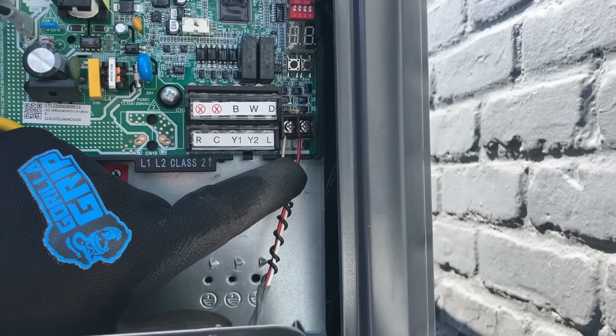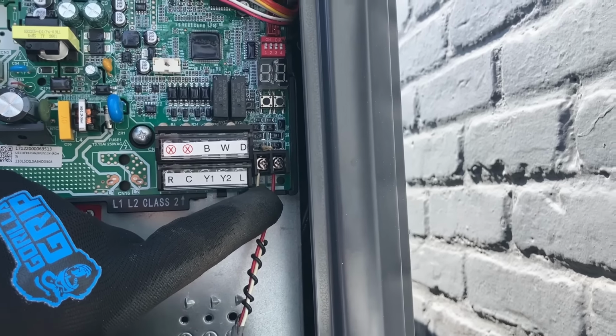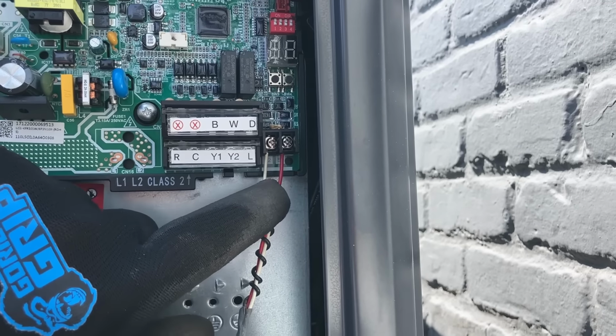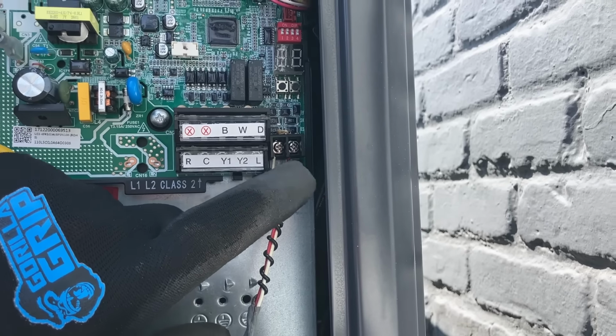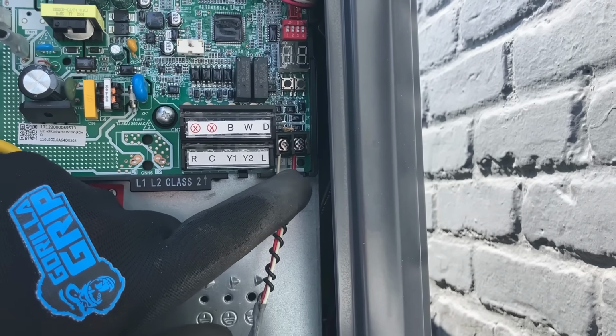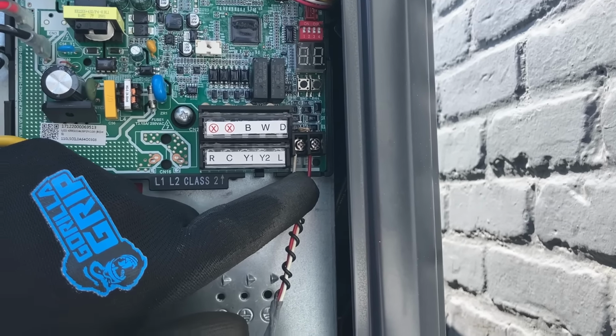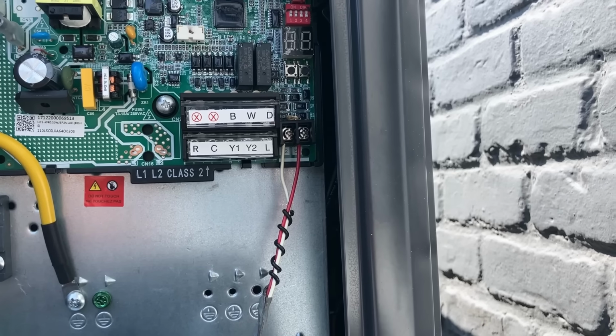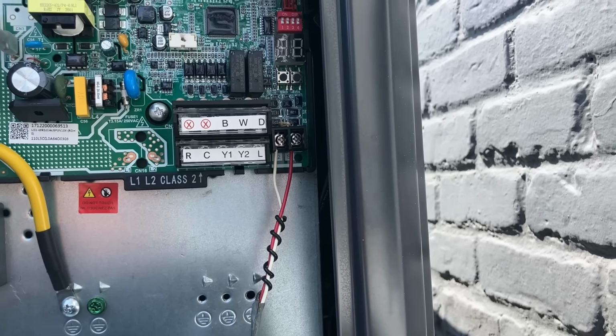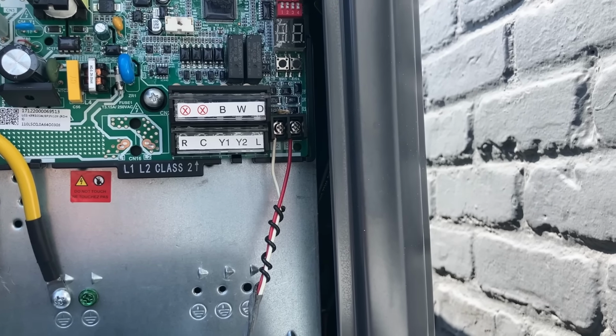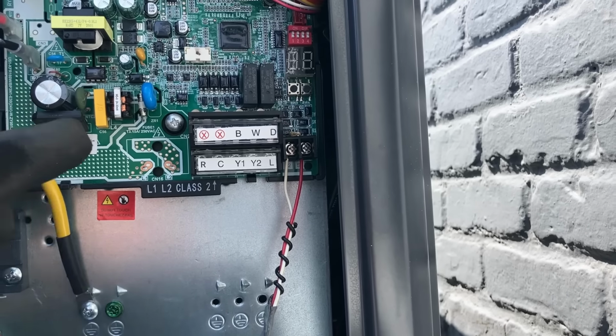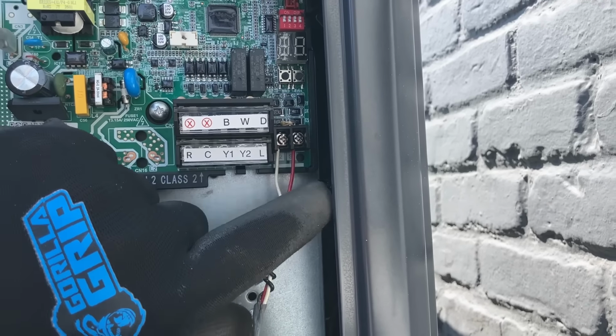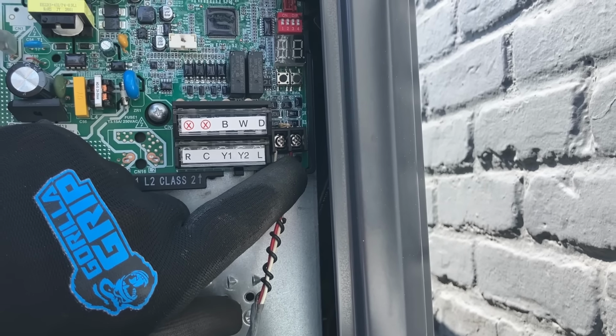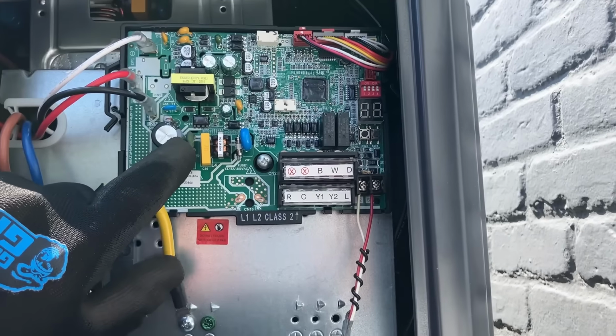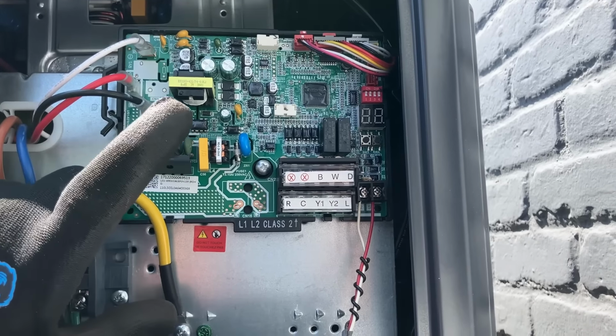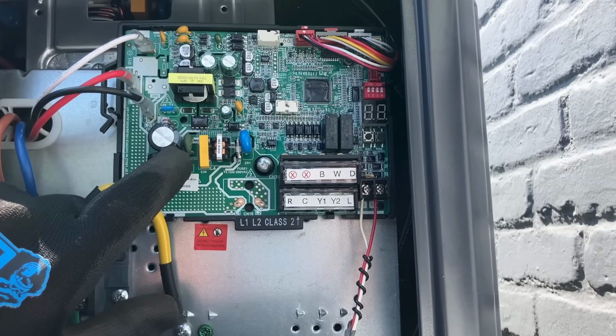These 2 wires here are connected to my S1, S2 terminals here at the outdoor unit. It's also connected to S1, S2 at the indoor air handler. We're using communication. This uses serial communication, which is RS485. Now, the manufacturer claims that it's non-polarity, but it does make a difference. Also, do not put 24 volts here, S1, S2, and think you're gonna be having a walk in the park. You will blow this board and you will be cursing yourself, not the manufacturer, because you messed up, okay?